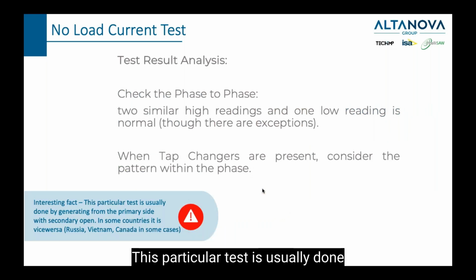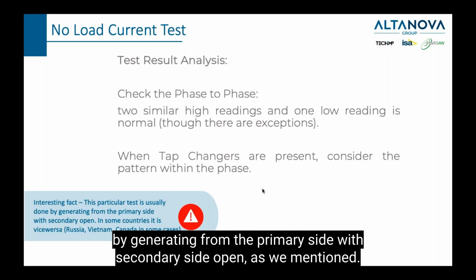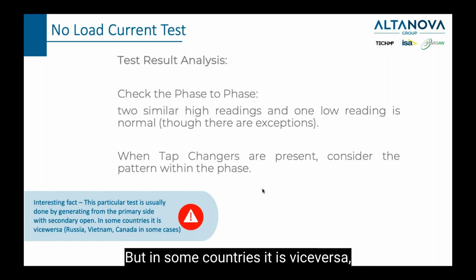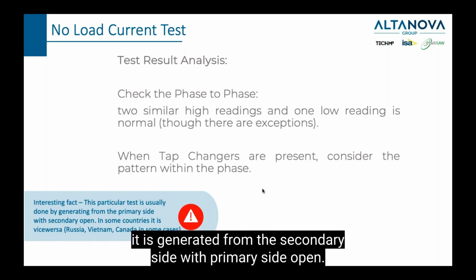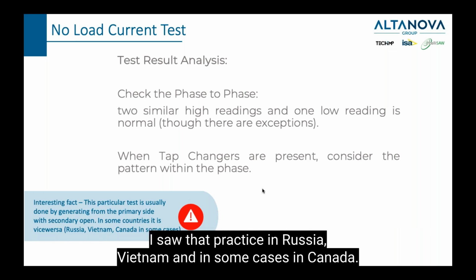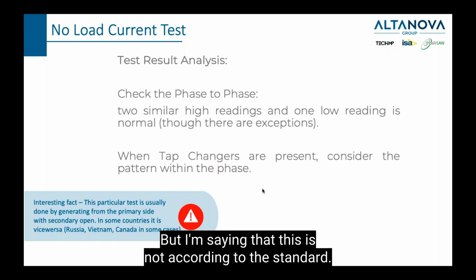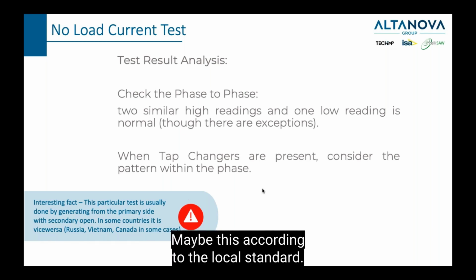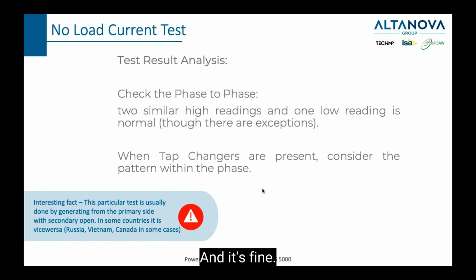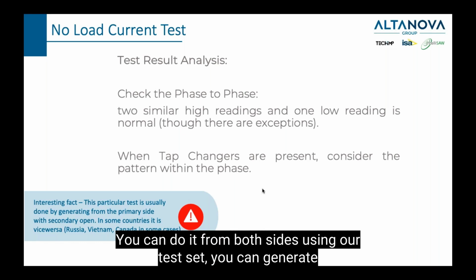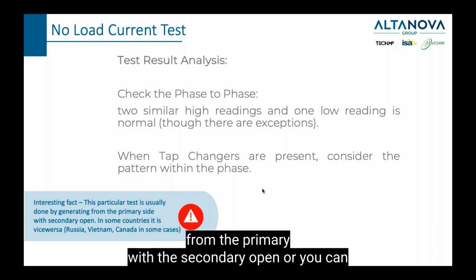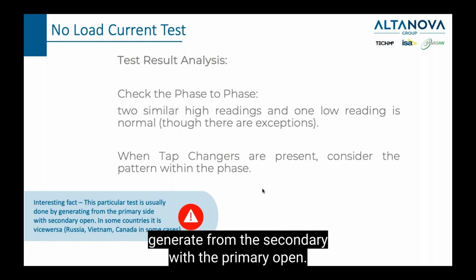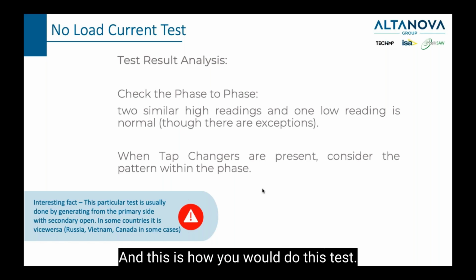Interesting fact, this particular test is usually done by generating from the primary side with the secondary side open, as we mentioned. But in some countries, it is vice versa. It is generated from the secondary side with the primary side open. I saw that practice in Russia, Vietnam, and in some cases in Canada. But I'm saying that this is not according to the standard. Maybe it is according to the local standard, and it's fine. You can do it from both sides using our test set. You can generate from the primary with the secondary open, or you can generate from the secondary with the primary open. And this is how you would do this test.